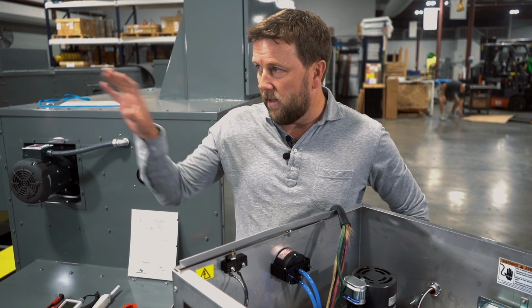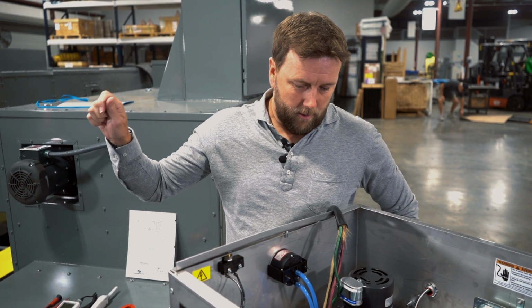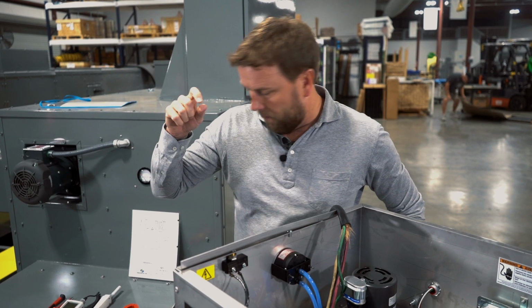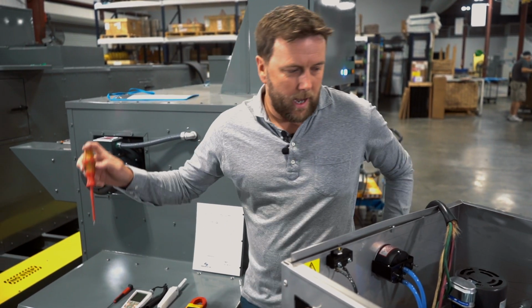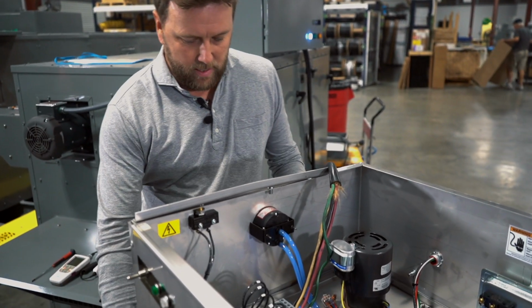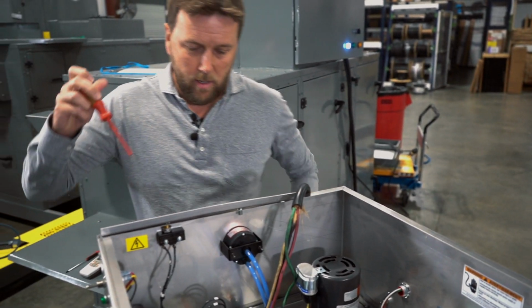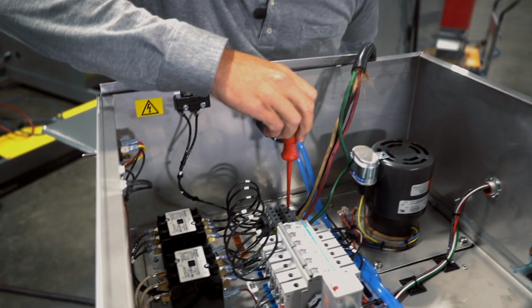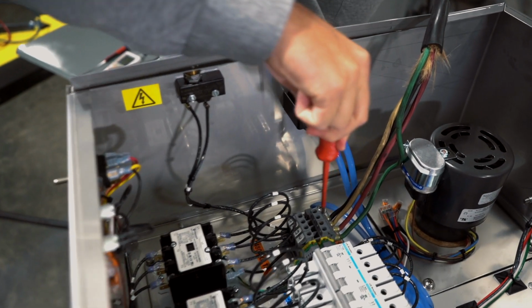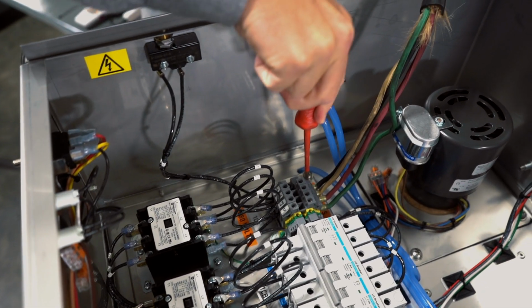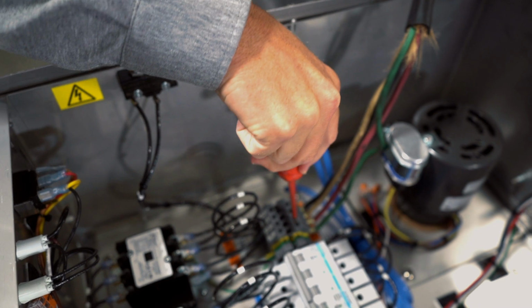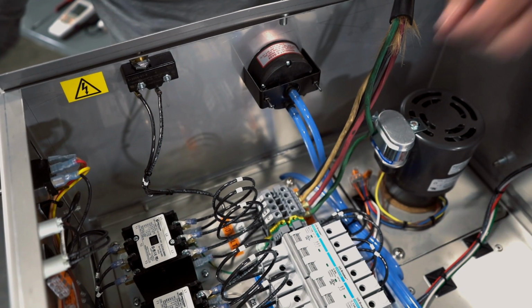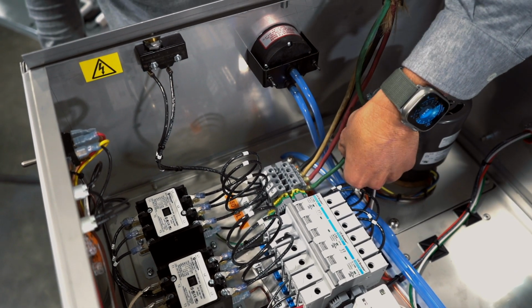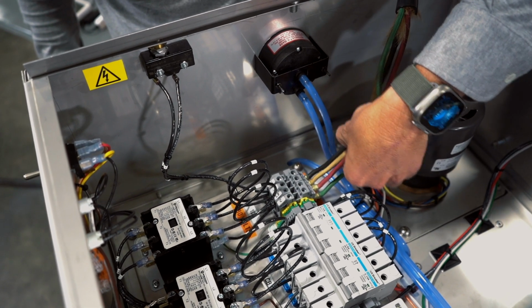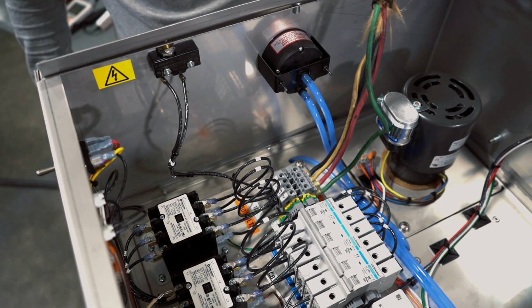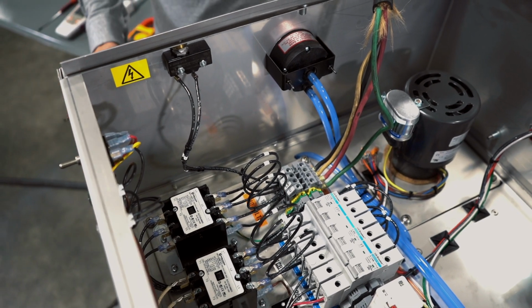With that being said, it is powered up. We do not have the disconnect thrown yet, but what we want to do is double check that every one of these terminals is fastened so it will not slip out, and with one hand only, reach in there and physically tighten these up. With the power off, you're always going to want to double check that the terminals do not have the potential to come loose and short out later on.